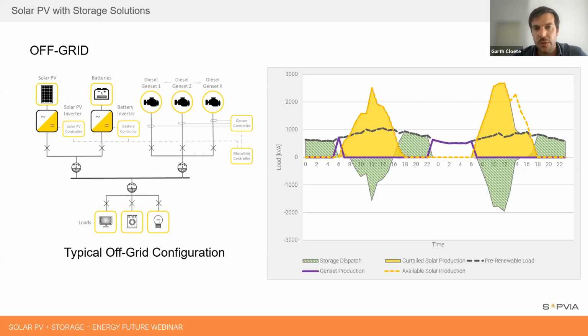On the right, the graph shows periods where you're still running diesel. Pushing for a 100% renewable fraction in any system is incredibly expensive—you'd end up designing for those 3 or 4 days of ongoing rainfall where you don't get enough PV, meaning you'd have to increase your solar PV size tenfold just to gain an additional 1 or 2% renewable fraction. That's really the limitation. These systems tend to have quite a bit of excess solar PV energy that you end up curtailing and not utilizing. It comes down to simulation and optimization around levelized cost of energy, which is really the driver for most renewable energy and battery storage systems: finding the most financially viable mix of energy sources to keep costs at a minimum.